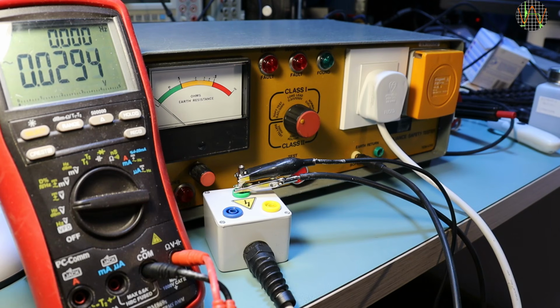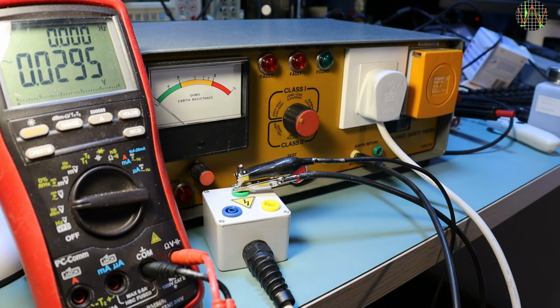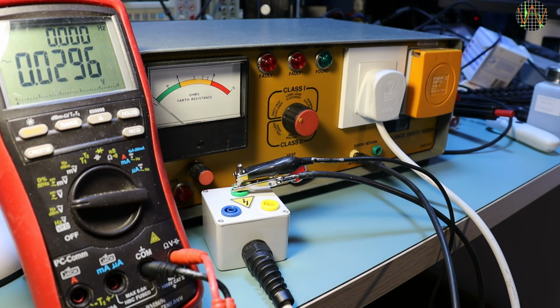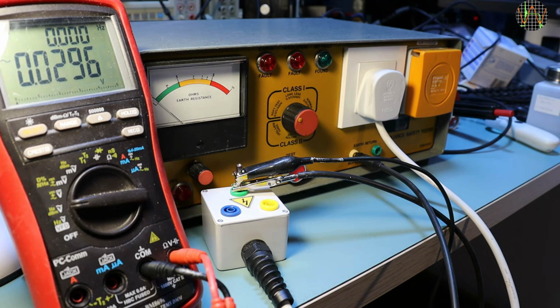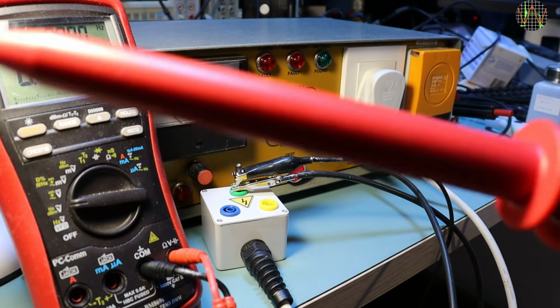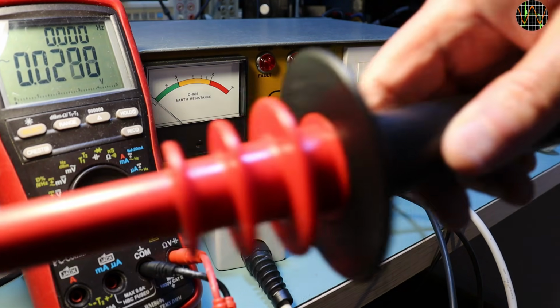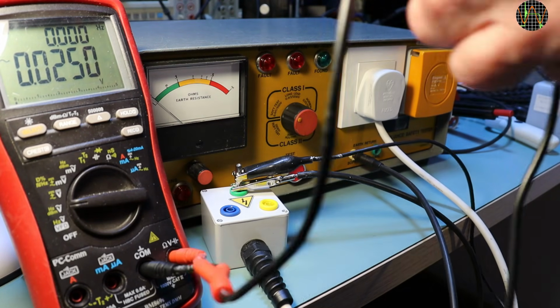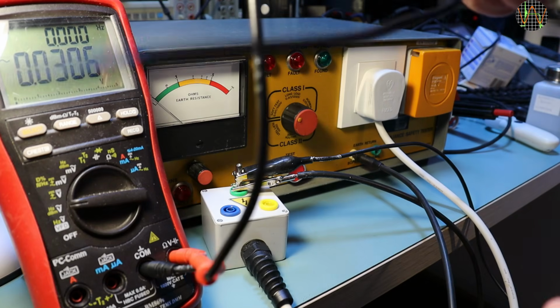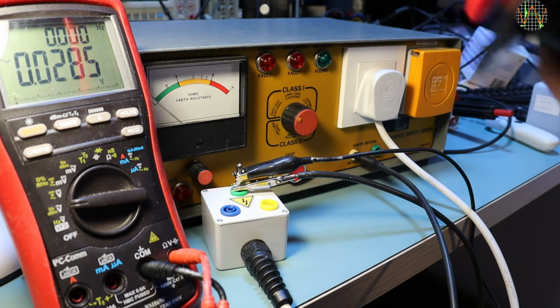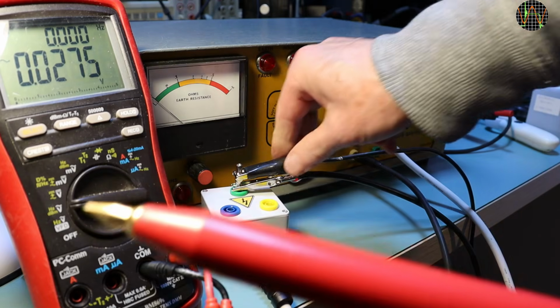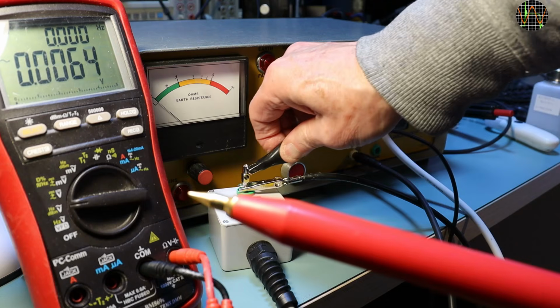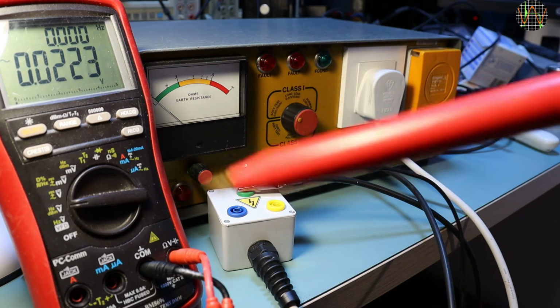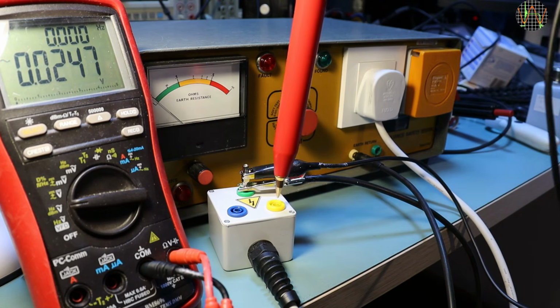Onwards to insulation. On class 1, live and neutral are shorted and high voltage is applied between these and earth. To measure it, I use this impressive high voltage probe rated for 40,000 volts. It divides by 1000, so 1000 volts shows as 1 volt on the multimeter. The low voltage outputs are connected to the meter, while one of the high voltage inputs is connected to the earth terminal of my box, and I use the probe to check the live or neutral sockets. That's not ideal because the tip is too wide to really connect. Let's see how we get on.